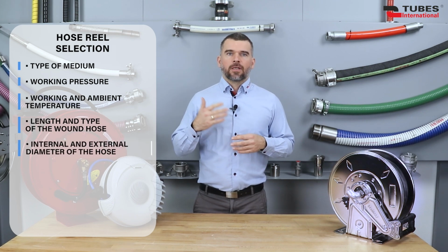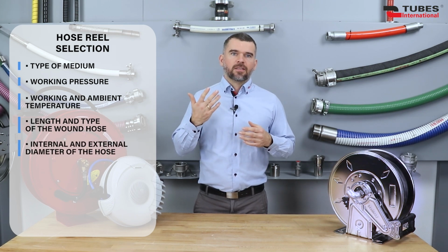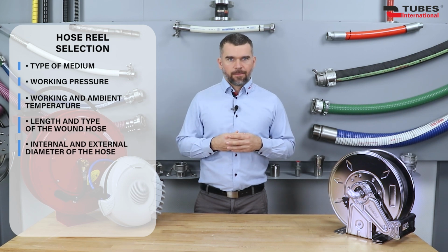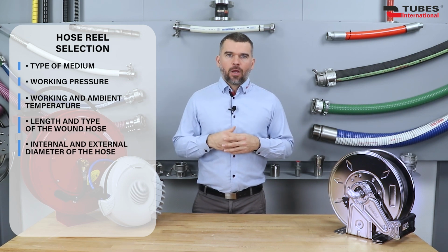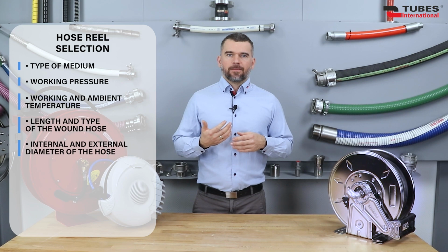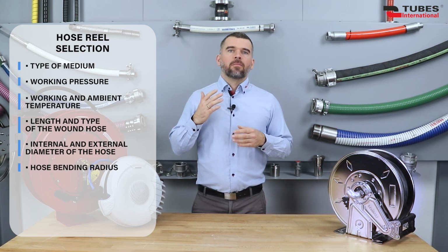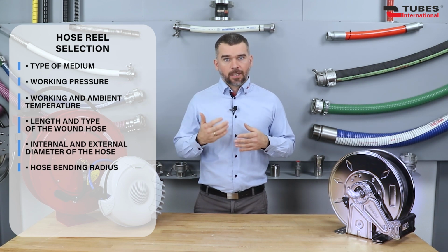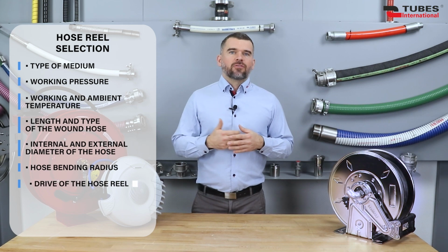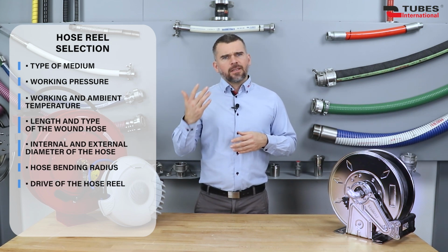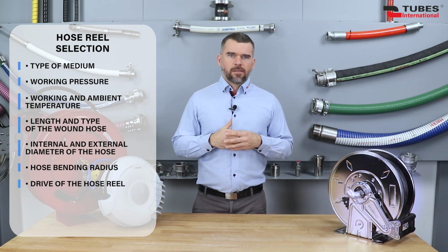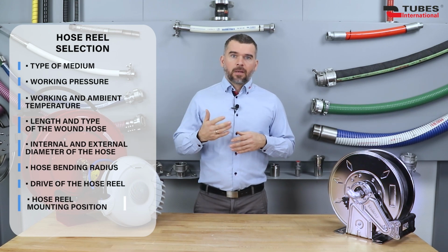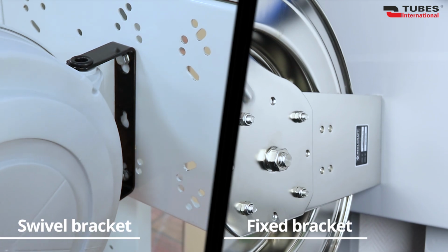Internal diameter of the wound hose, which affects the selection of the swivel joint. External diameter, which determines the size of the reel. Bending radius of the hose, which must be at most half the diameter of the reel spool to prevent hose kinking. Type of reel drive mechanism. This topic will be covered in more detail later in the video. Mounting method and mounting location. Floor, wall or ceiling.